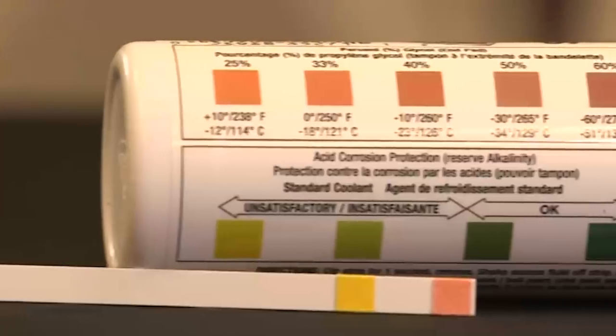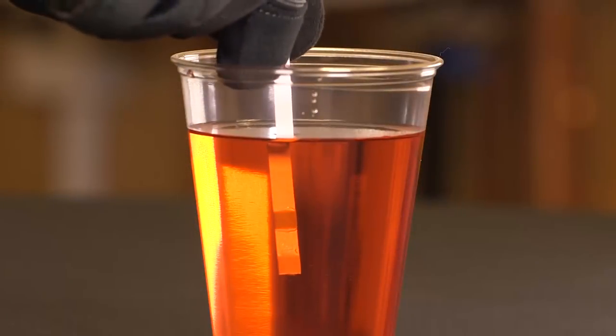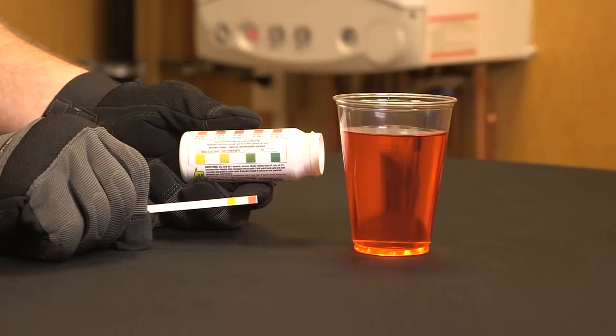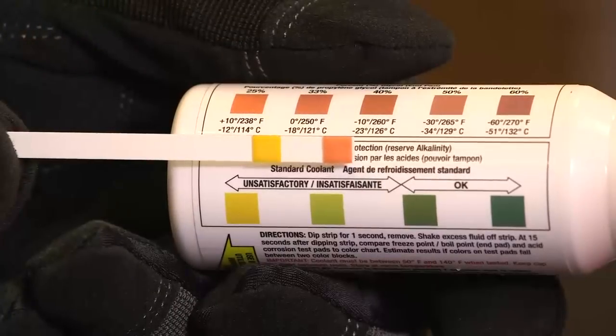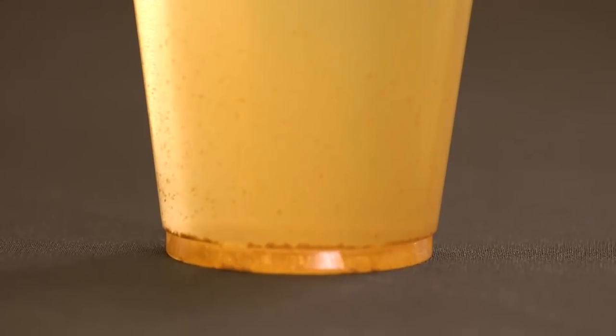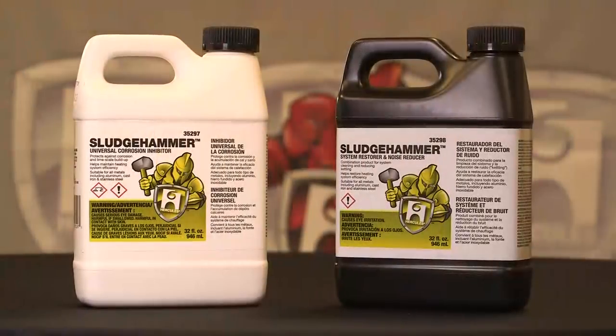Using the color charts on the back of the bottle, dip the strip in the water for one second, shake off the excess water, and wait up to 15 seconds for the color to change. If the level is low, add corrosion inhibitor. If rust or sludge is visible, treat with System Restorer and Noise Reducer.